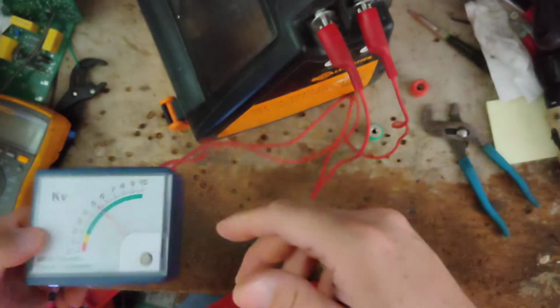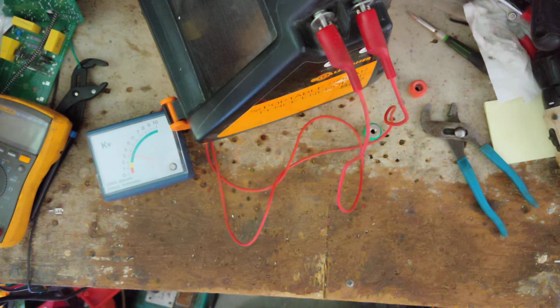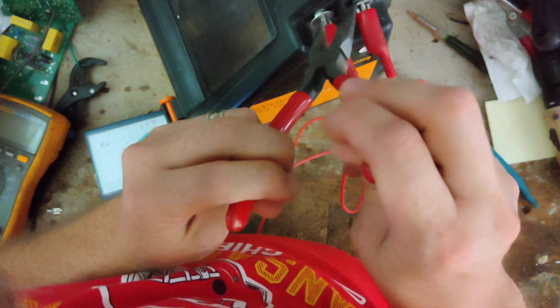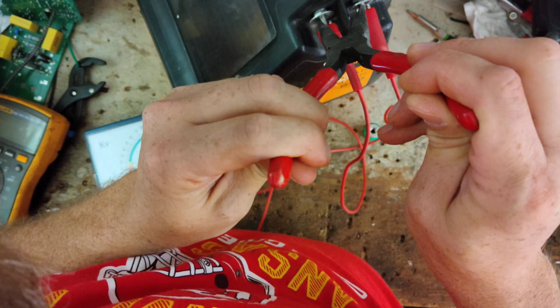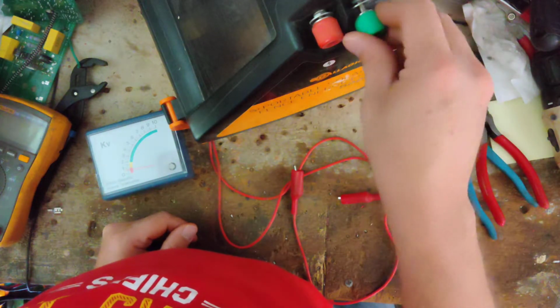On S22, this is normal. This on right at the fence and ground, it's about normal. It should be 5.5, give or take. And we're reading about 6. Let's put a pair of needle nose across it, and we'll see. Almost sparks, so the load's working fine on it. So at the moment, nothing wrong with it.